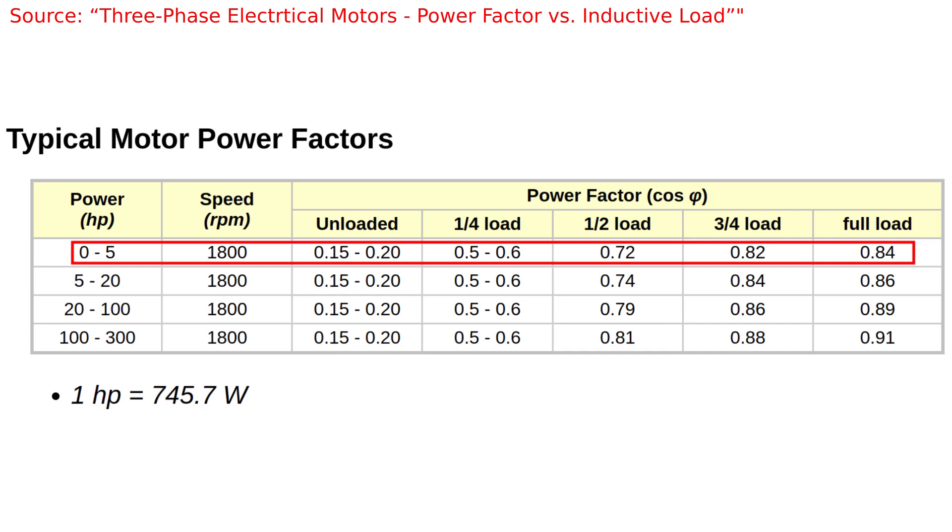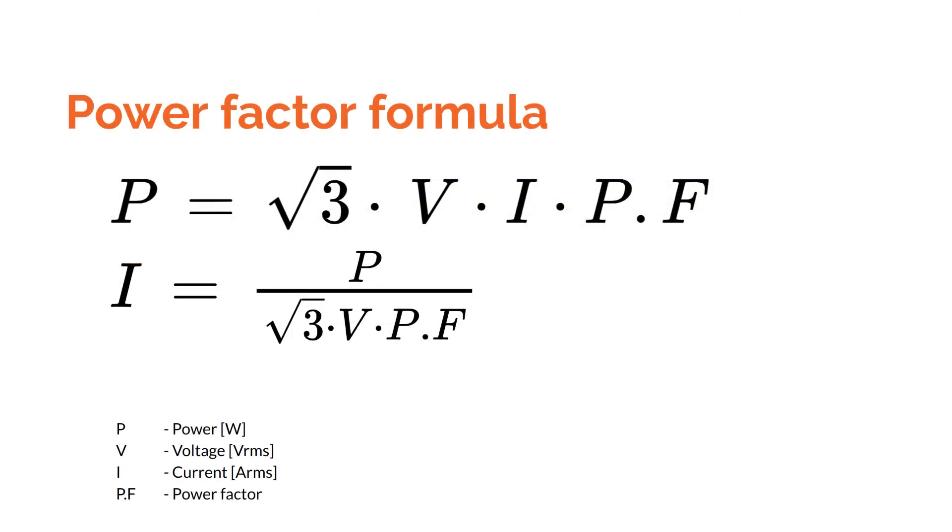So, why did I use the power factor at full load in the equation when calculating the continuous current? According to the equation, because the power factor is in the denominator, a smaller power factor would mean I would need to handle a higher current. I used the full load power factor in the equation because the highest current consumption of a motor is at full load, despite having a higher power factor.